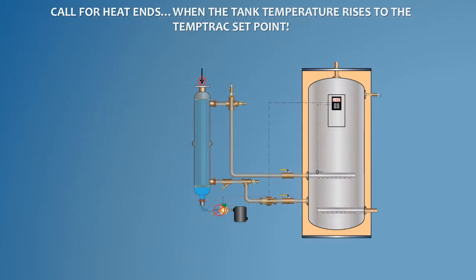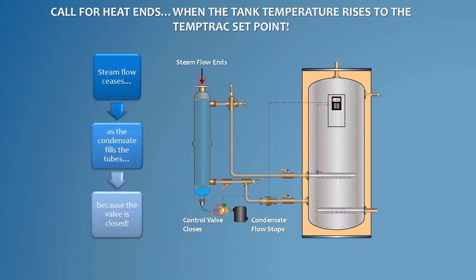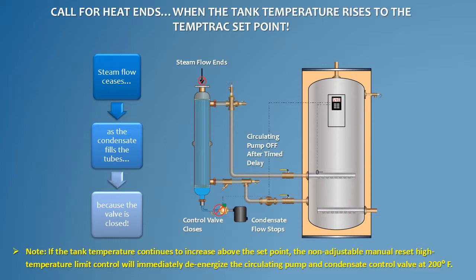When demand for hot water ends, the stored water temperature rises to the TempTrac operating set point. The condensate control valve is immediately de-energized and closes. The trapped steam continues to condense until the heat exchanger is entirely filled with condensate and the flow of steam is stopped completely. The circulating pump will continue to operate for approximately 30 seconds to extract and transfer any residual heat from the heat exchanger into the domestic water in the tank. When the time delay ends, the circulating pump is de-energized and stops the circulation of heated water from the heat exchanger to the storage tank. If for any reason the water temperature in the storage tank should rise above the TempTrac operating set point, the non-adjustable manual reset high temperature limit control will immediately de-energize the circulating pump and the condensate control valve.